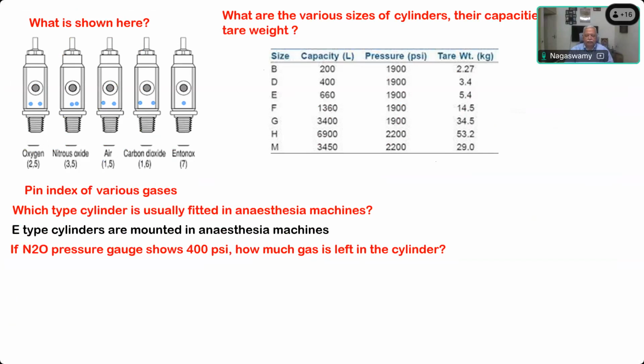It has to vaporize and become a gas. So till the last drop of liquid nitrous oxide is there, it will show the same pressure, and then suddenly start decreasing when the last liquid has become gas and it starts coming out. Only at that time will the pressure start reducing. So people thought, why unnecessarily have a pressure gauge for that, which will constantly show only 750 until the final stages? But later on, you find all your machines have a pressure gauge for nitrous oxide also.